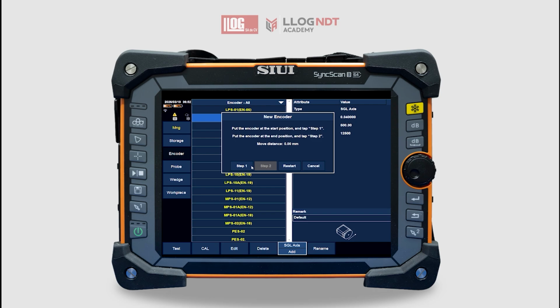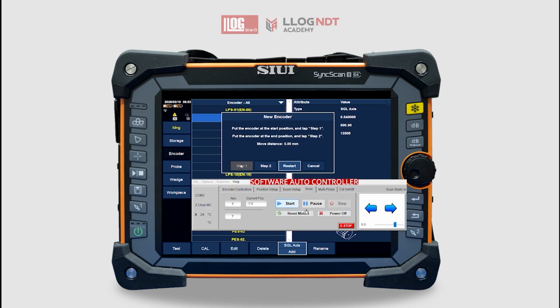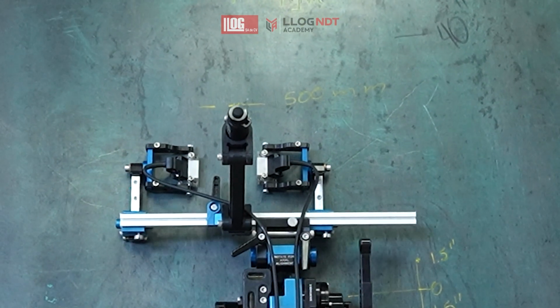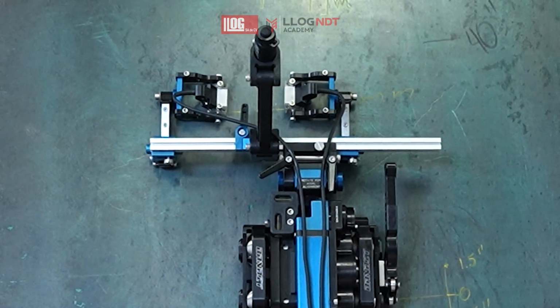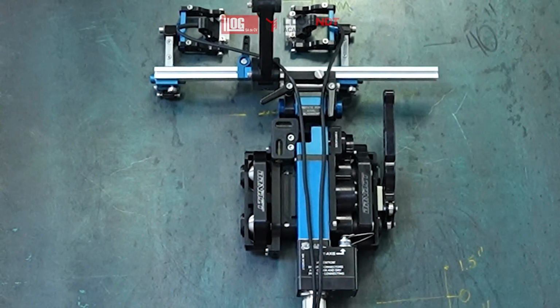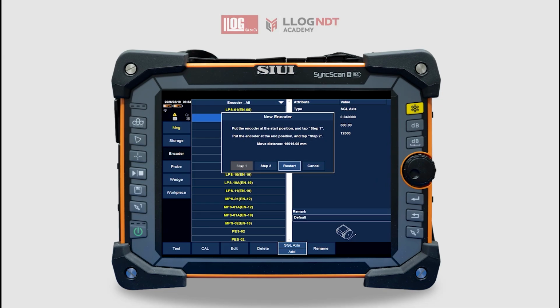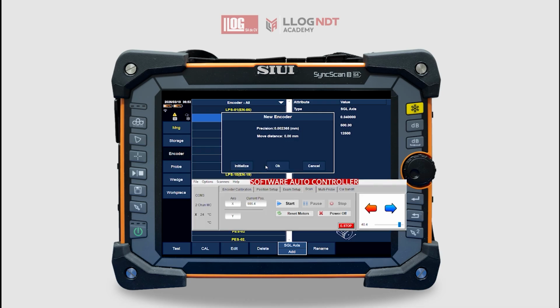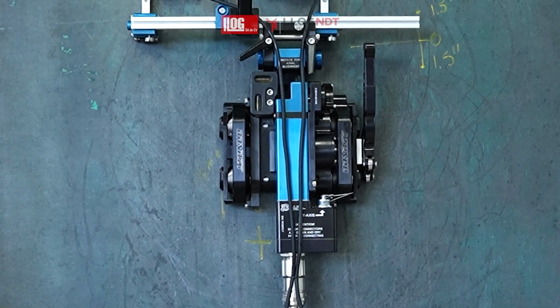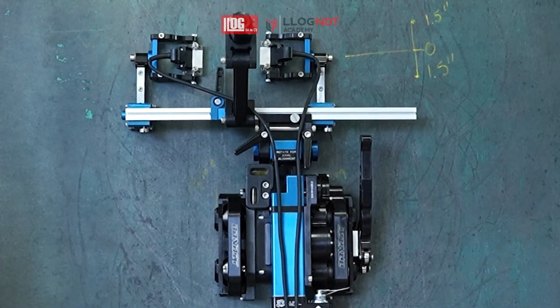Once the sensors are in position, press Step 1 and move the encoder to the final position. Once the encoder reaches 1,000 millimeters, press Step 2 and return it to the starting position. Once the travel is complete, the instrument automatically calculates the pulses per millimeter required to cover the reference distance. Press OK and assign a name to this new setup.